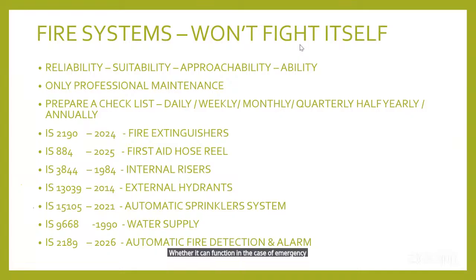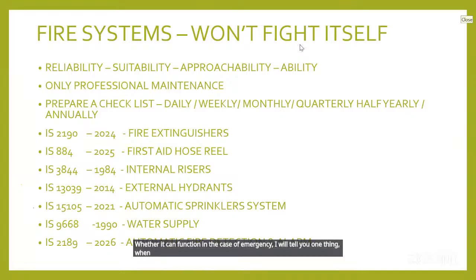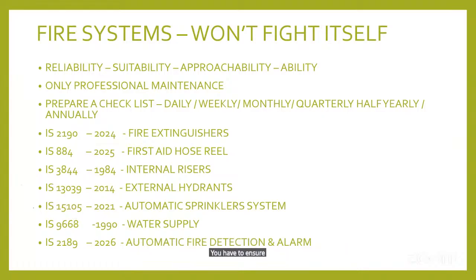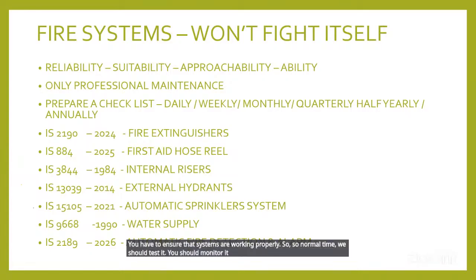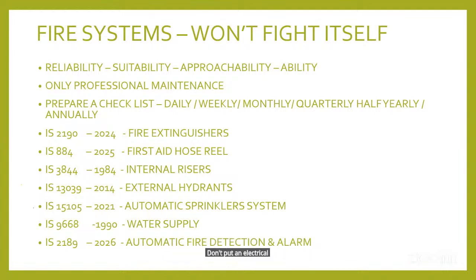I will tell you one thing: when an extinguisher cannot function in normal time, it will not function in an emergency. So in normal time, you have to test it and ensure that the systems are working properly. You should monitor it and see it visually. That is reliability. And then suitability. According to the risk, you have to select the extinguishing medium. Don't use foam or water type on an electrical item. That is not suitable.